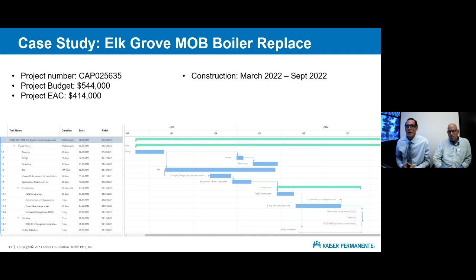In this case, we had an OPR, and the OPR literally said replace in kind. There are some references to meeting current energy standards, but that's kind of wishy-washy. In this particular project, there was no basis of design—our engineer of record didn't do any basis of design or calculations. There was no commissioning, no looking at the system, no assessments. They did not look at historical energy data, and they didn't even check the sizing of the boiler.